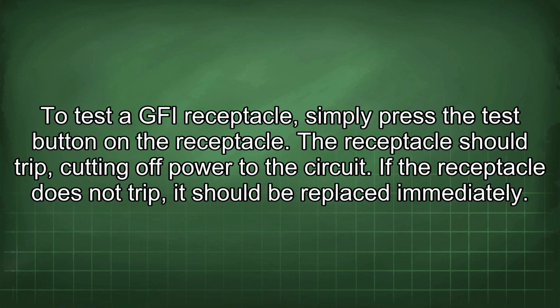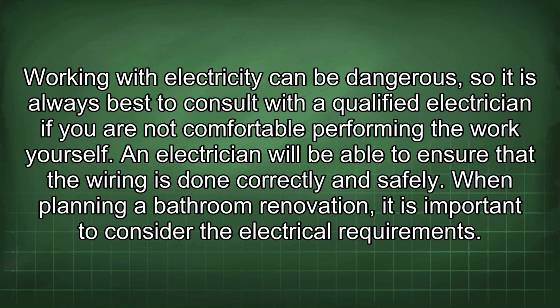To test a GFI receptacle, simply press the test button on the receptacle. The receptacle should trip, cutting off power to the circuit. If the receptacle does not trip, it should be replaced immediately. Working with electricity can be dangerous, so it is always best to consult with a qualified electrician if you are not comfortable performing the work yourself. An electrician will be able to ensure that the wiring is done correctly and safely.